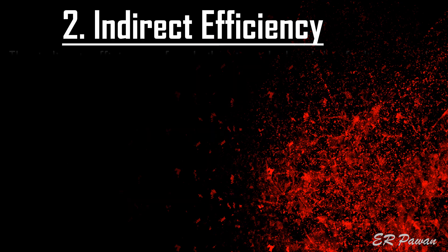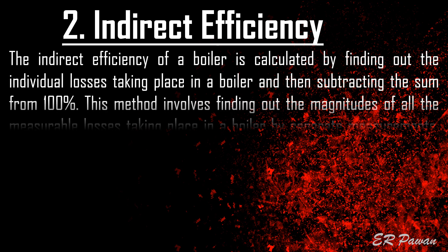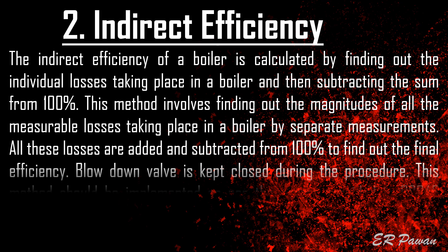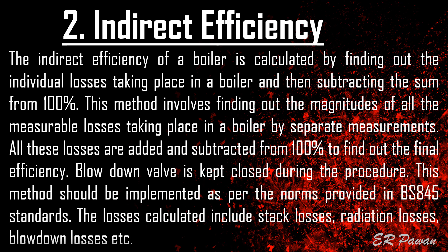Indirect efficiency of a boiler is calculated by finding out the individual losses taking place in a boiler and then subtracting their sum from 100%. This method involves finding out the magnitudes of all measurable losses by separate measurements, adding all these losses, and subtracting from 100% to find the final efficiency. The blow down valve is kept closed during the procedure. This method should be implemented as per the norms provided in BS 845 standards. The losses calculated include stack losses, radiation losses, blow down losses, and others.